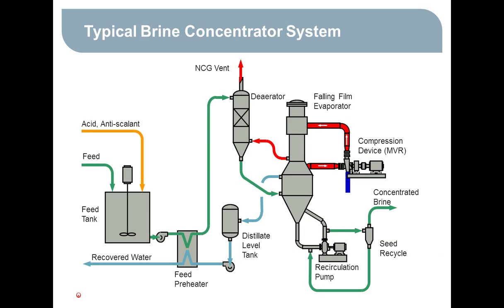This is a typical brine concentrator system in all its required components. Basically, if you start over on the left, you'll see the feed stream goes into a tank, and in the tank, some acid is added, and that's to convert any alkalinity that's in the feed to CO2. That feed then is preheated by exchanging heat with the outgoing distillate or recovered water in a plate-type heat exchanger, which is called the feed preheater.